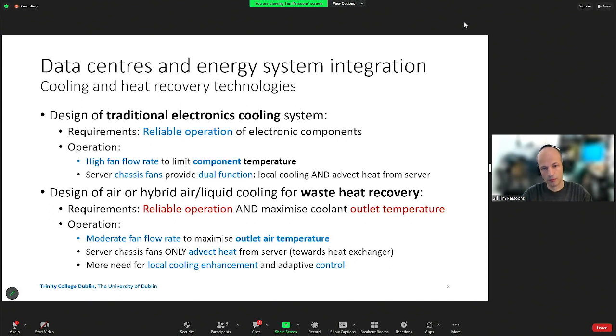So that means that we want to lower the fan speed slightly so that, in balance, your outlet air temperature goes up. And we want to reach a situation where the server chassis fans only advect heat from the server, but that local cooling is dealt with by other means, which could be liquid cooling, or it could be some adaptive local air cooling. And I'll show you some examples of what that might look like in this presentation.